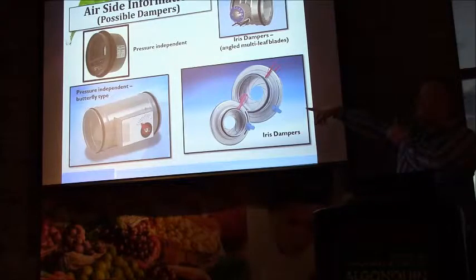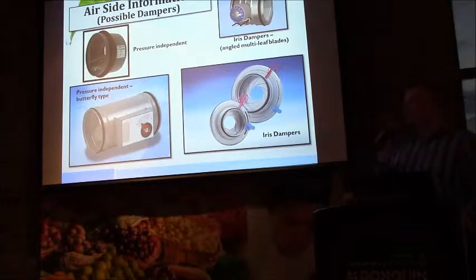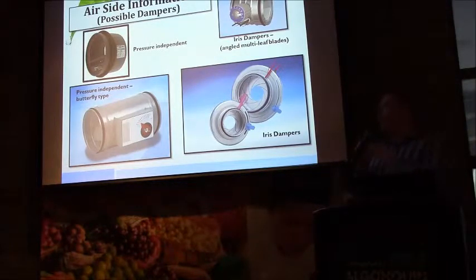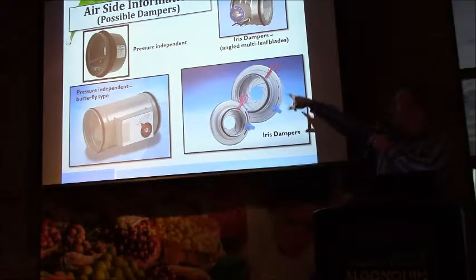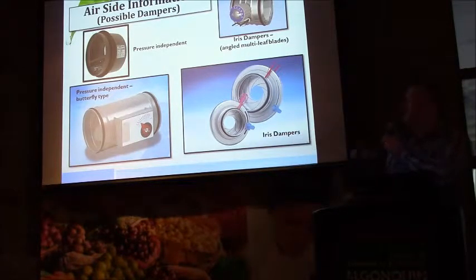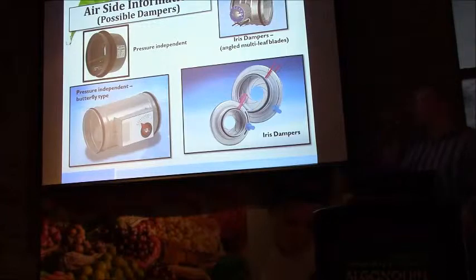The top damper is very similar to the iris damper. Its design is such that the blades are angled in the direction of flow to get better static regain and create less flow generated noise as a consequence of this tripping surface at the iris. And then this other device is a spring calibrated pressure independent butterfly style. So there's an inflatable element behind the blade to position the mass flow of air that we need. Conceptually, the pressure independent flow regulating device and an iris damper are very similar in price. The pressure independent butterfly type with that spring calibration is in the neighborhood of three times the expense. And these are somewhere in the middle of that.